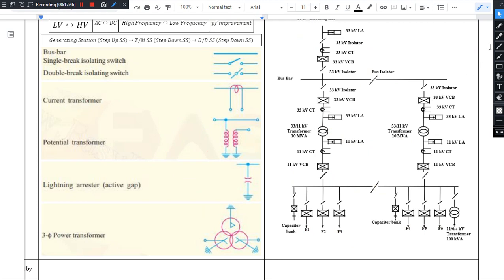The purpose of a bus coupler is as follows: suppose a PTR goes under maintenance. Normally, the feeders connected to it would have no current supply. To avoid this, we use the bus coupler to share the load from the PTR under maintenance to another PTR. The bus coupler allows the load to be transferred between buses so that supply to feeders is maintained during maintenance.